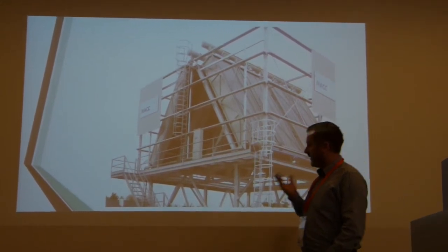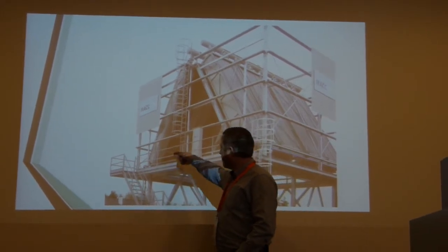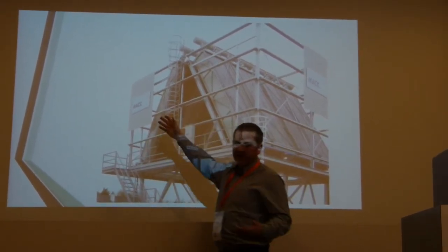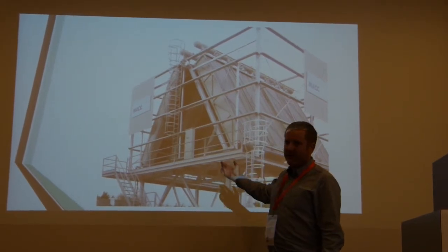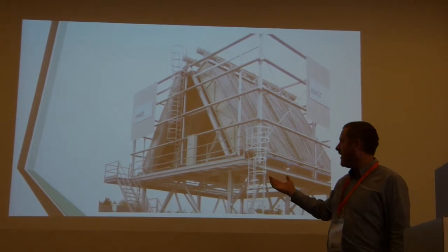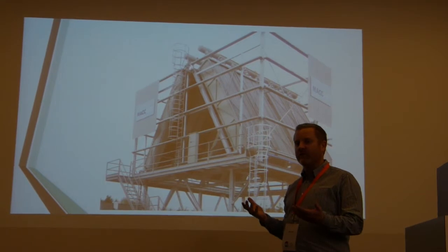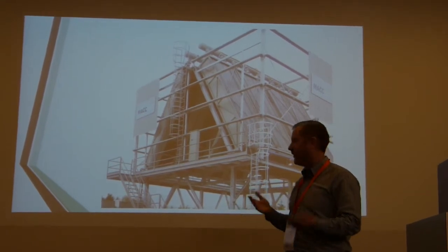And the innovation that we have, or the key thing that you will notice if you're familiar with that type of technology, is that we have a number of fans located right underneath the tubes, rather than this large 10-metre fan. And what this allows us to do is to make some intelligent decisions around how fast these fans should be run, which fans should be run, which side should be run, which side should be turned off.